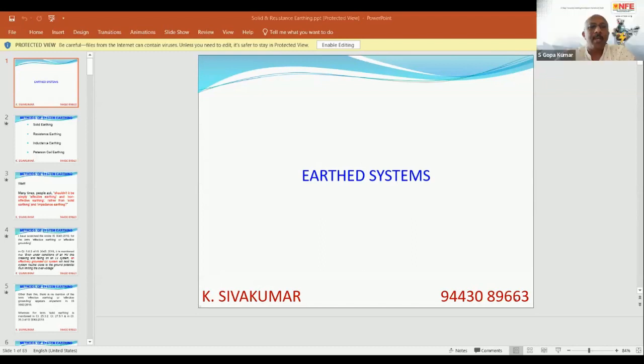Then there is a question: how can an earth fault in an MV system be cleared in 10 milliseconds when the circuit breaker, VCB or SF6, tripping time is 40 to 50 milliseconds? Sir, whenever we say clearing in this sense, it is the relay time. Today, arc protection devices are capable of sensing and sending a signal to the breaker in 10 milliseconds. Whenever we talk of any protective device, the time discussed is that of the protective device. I am not discussing the circuit breaker, because circuit breaker tripping times can vary depending upon the rated voltage, the fault current to be interrupted, the mechanism, and the auxiliary voltage. There are n number of variants due to which the operating time of the switchgear can vary. So this 10 millisecond I am talking about is that of the protective device. You add whatever your switchgear operating time is to that. That will be the total fault clearing time.